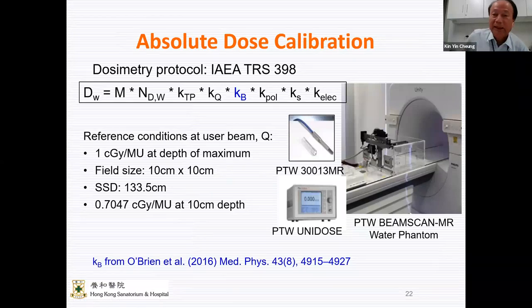Now, the next thing we need to do is the absolute dose calibration. We have to use a water phantom, and we use the IAEA TRS-398. This equation should be familiar to you, except this factor, kB, is the factor to correct for chamber response due to the magnetic field effect. This factor is available from a paper by O'Brien in the Medical Physics journal.